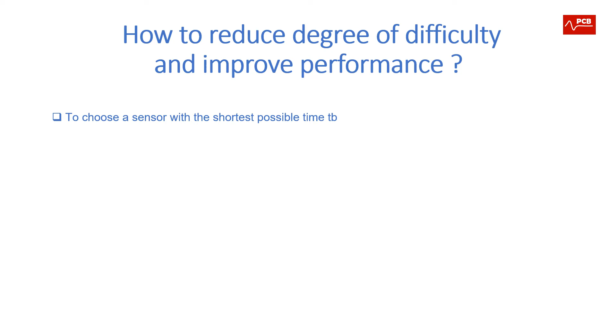How to reduce degree of difficulty and improve performance of control system. First of all, choose a sensor with the shortest possible balancing time, and install it as close as possible to the valve, or even in the heat exchanger in the domestic hot water preparation process. And use pressure independent valves, which eliminate pressure disturbances and ensure proper valve authority.